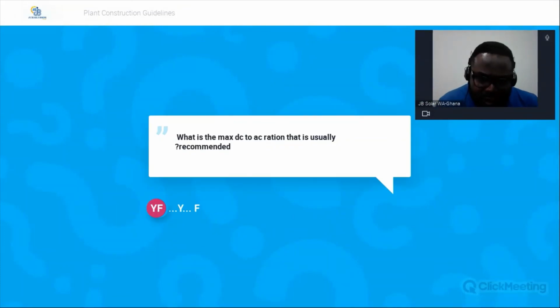Yusra Fatima is asking, what's the max DC to AC ratio that is usually recommended? Beautiful question. For Huawei inverter systems, Huawei recommends a DC to AC ratio of 1.3. You can go up to 1.4, but if you're asking for a recommendation, it's 1.3. As a matter of fact, if you put optimizers on your roof with the panels, you can do a long string design, which can take you up to 1.6 or 1.7, but that's only if we have optimizers. Without optimizers, the adequate Huawei system ratio is 1.3. I hope that answers your question.